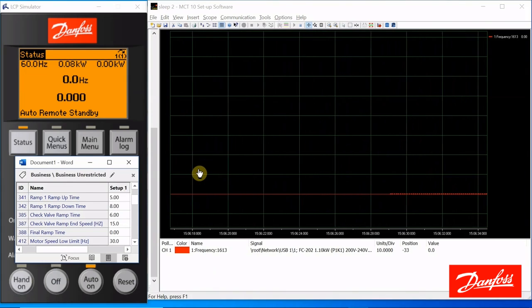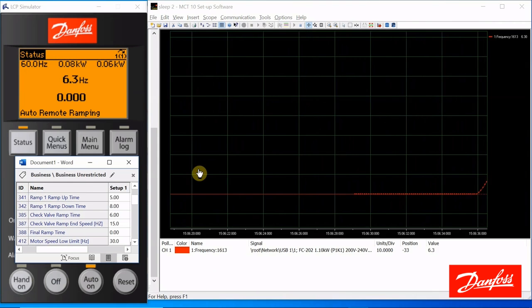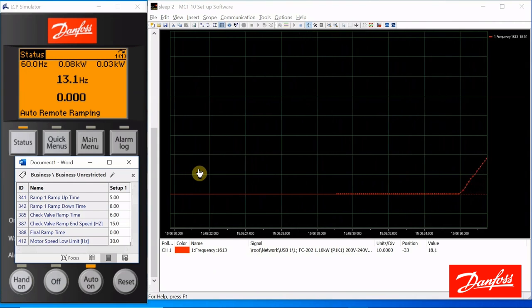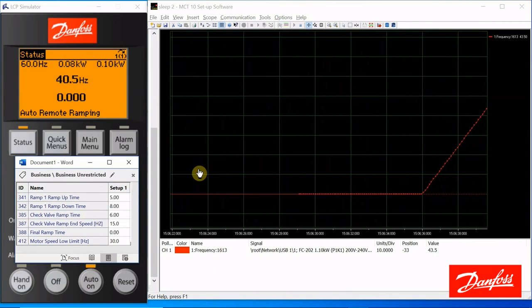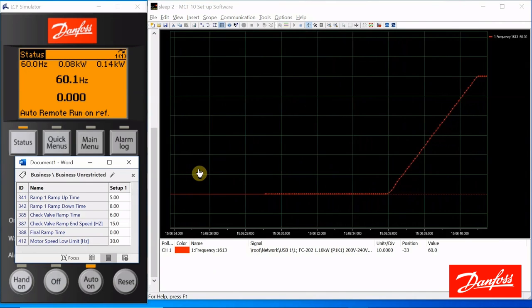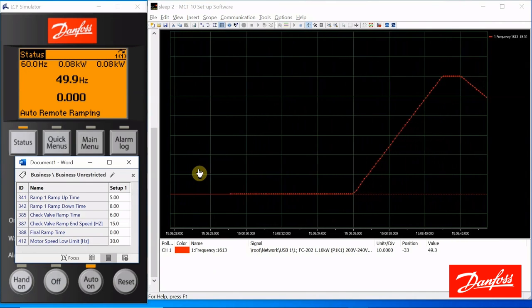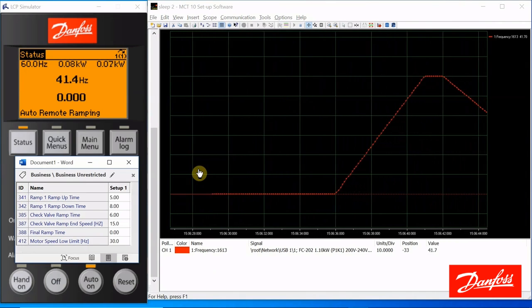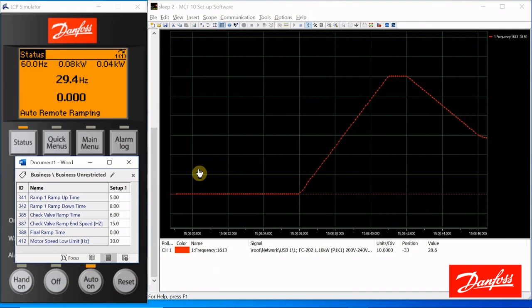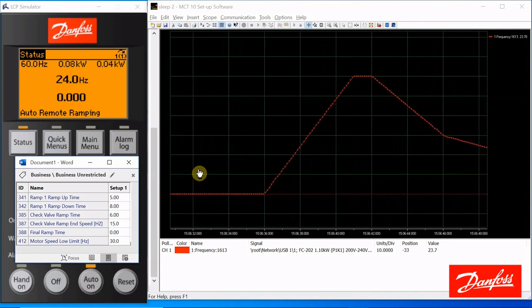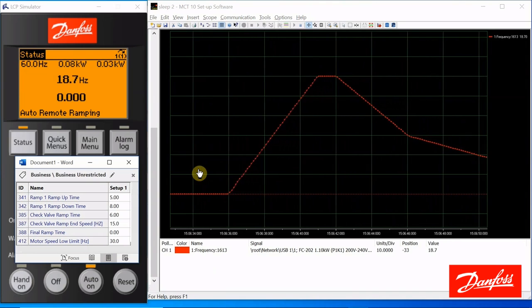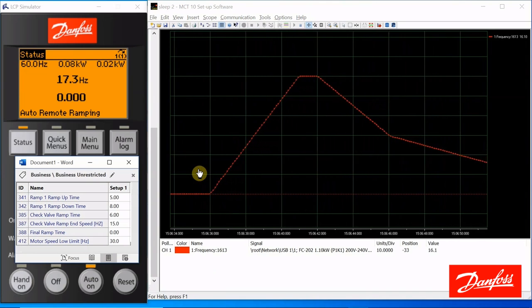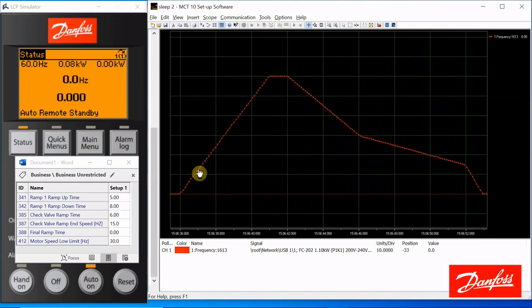Okay, once again, we'll give a start command. Take 5 seconds to get up to 60 hertz. Stop command. 8-second ramp down pace. Reaches 30 hertz. It switches to 6 seconds to get down to 15. And then it takes 1 second for that final ramp. That's all there is to it. That's it. Thank you for listening.